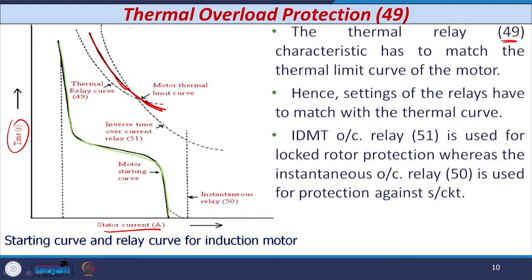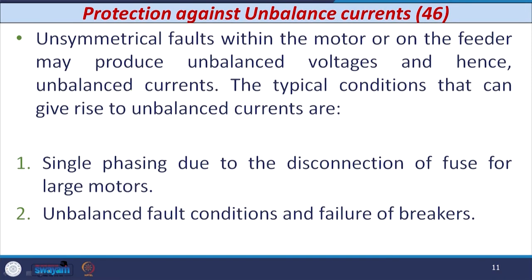The next phenomenon is protection against unbalanced current. The relay number given to the unbalanced relay is 46, also known as negative phase sequence protection. In case of unsymmetrical faults that may occur within the motor or on the feeder emanating near the motor, these may produce unbalanced voltages and hence unbalanced currents.